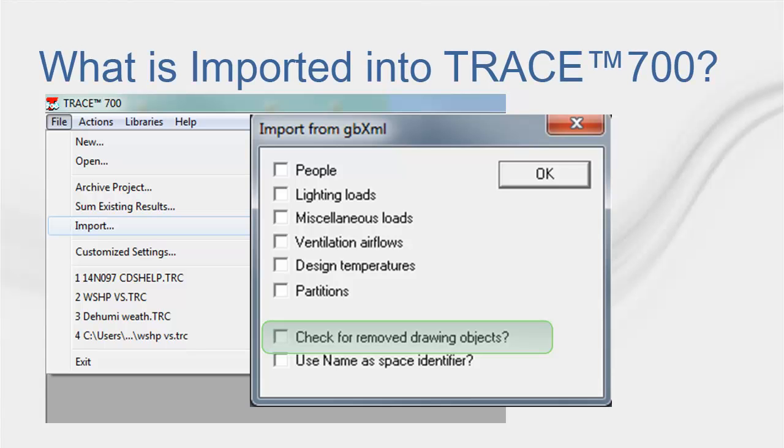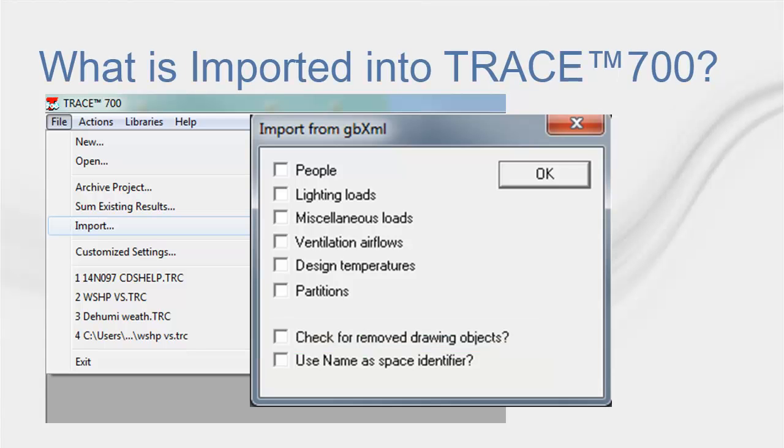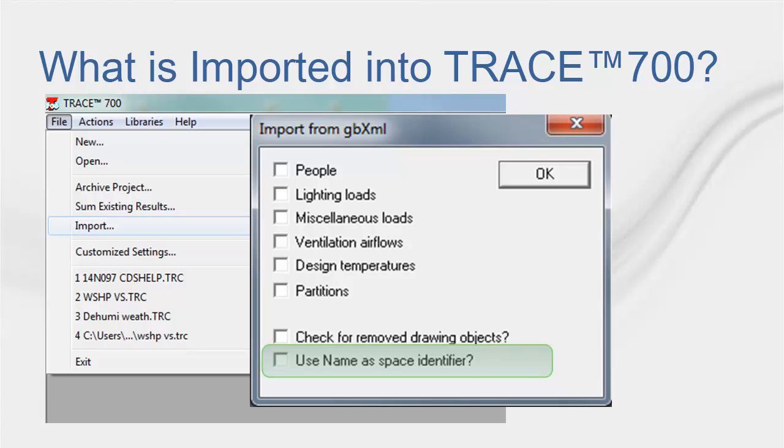Importing non-needed partitions might make temperatures drift or might take very long calculation time if there are many partitions in the building. The Check for Remove Drawing Objects option allows Trace 700 to remove any objects that were removed from the GBXML file after the first input into Trace. The Use Name as Space Identifier option assigns the name to each room from the name attribute created in the CAD program. If unchecked, the room name in Trace will be from the ID attribute in the file. For example, Revit uses the name attribute.